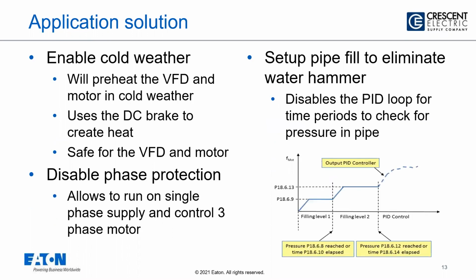There is a cold weather function in case the motor ambient becomes cold. In order to start the motors, we have a feature within the drive that preheats both the drive, the heat sinks, and also the motor by applying a small DC current for a small duration of time, and that is perfectly safe for the VFD and the motor. In that way, it brings up the temperature and starts the pump motor.